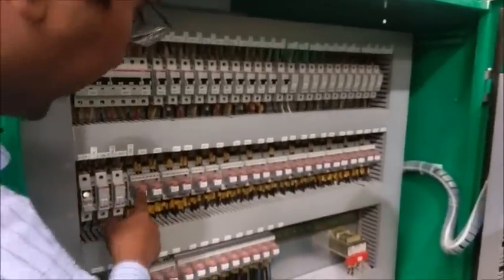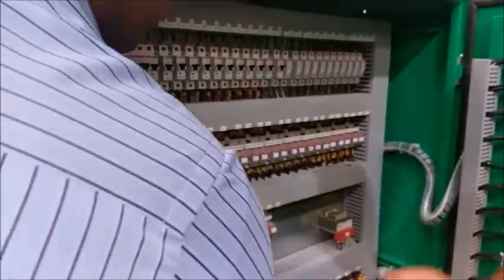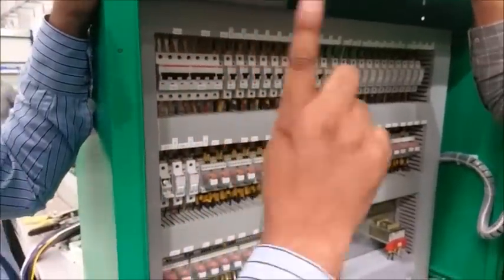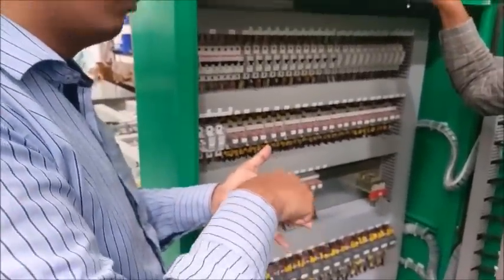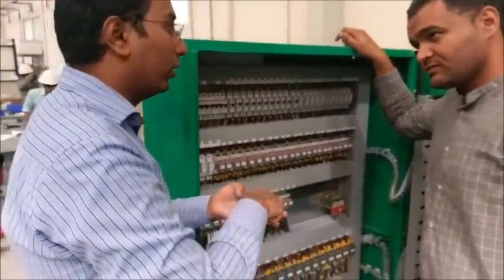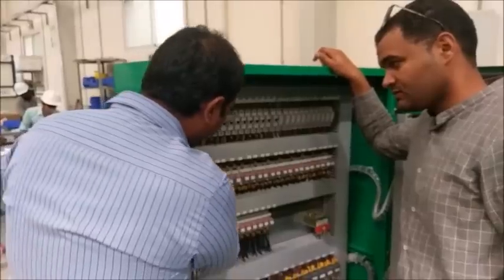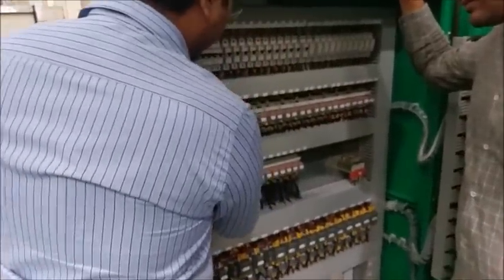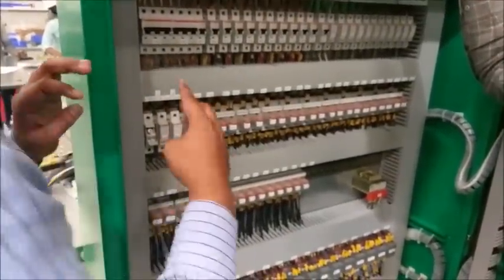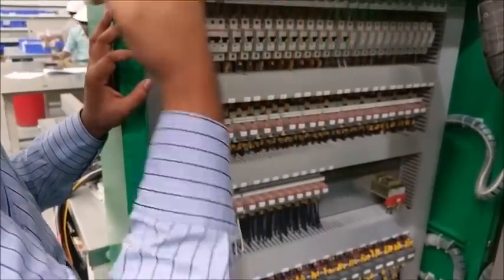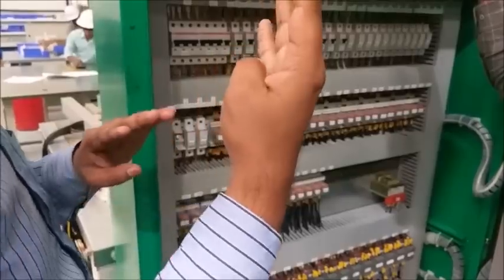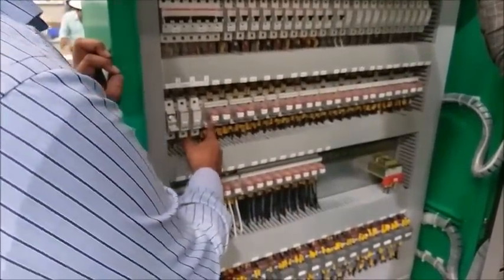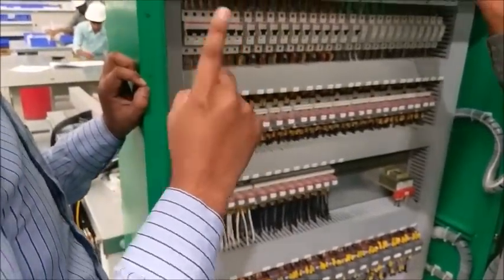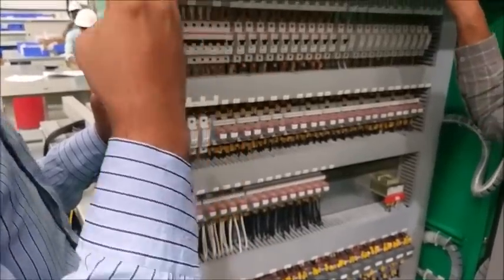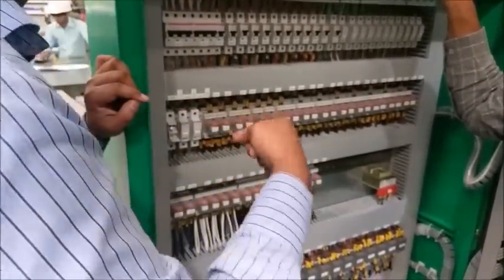Now this plug-in relay, what happens? When only one contact is available and we have to use multiple contacts, like for fire alarm, for override, for BMS, and for individual, but we have one contact only, in that case we use this relay. That contact will energize this relay, and then this relay will give us 4 contacts. In reality we have only one command, but we need 4 commands. So this is command multiplication.